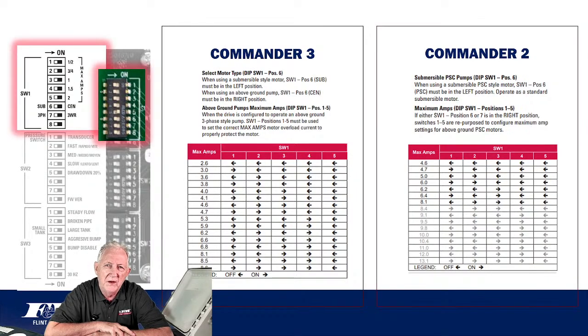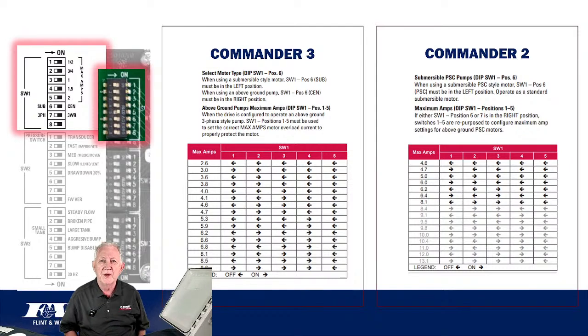I don't know, what would that be, 1.5 horse maybe motor? But you come down to that 6.2 max amps, and right there, if you go across, it's going to tell you that position 1 is going to be in the off position, position 2 is going to be in the on position, and then you go across and you know how to set those dip switches up based on max motor amps.